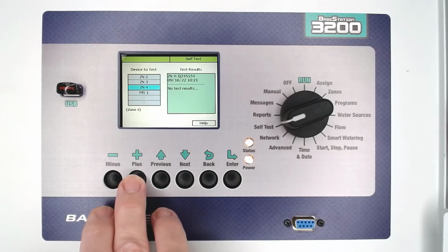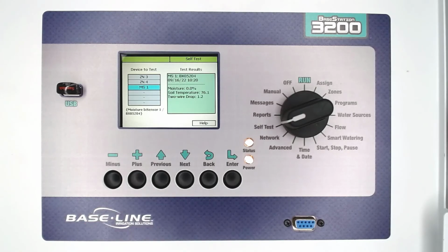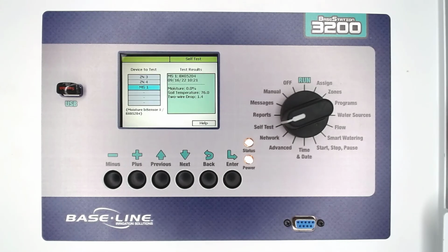Scroll through the list until you find the device you want to test. In this case, it's Moisture Sensor 1. With MS1 highlighted, press Enter to start the test. Moisture Sensor 1 reads 0% moisture, but it also reads 76 degrees temperature. This information tells us the controller can communicate with the sensor, but the data appears to be incorrect.